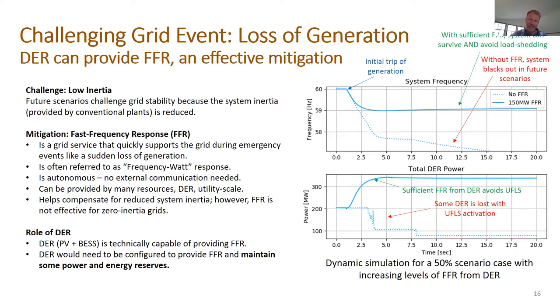This is a service that can be applied at the distributed resources across the grid, where all of these resources are watching system frequency for a sudden event like this. If they detect an event, they're able to quickly respond by injecting power and helping support the grid. The sensitivity that we're showing here on the right in the solid blue lines shows the same case with the same loss of generation contingency simulated, but now with FFR applied across the DERs on the grid. You can see that frequency initially goes down as would be expected for any event like this, but then it quickly stabilizes just slightly above 59 hertz.